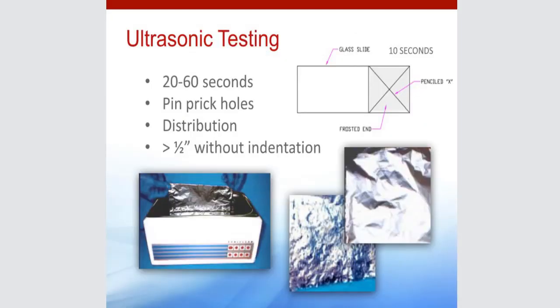Speaking of ultrasonics, these are my 2 public service announcements to deal with ultrasonic units. You want to make sure that you're following your IFUs for ultrasonic testing to make sure that your unit is functioning appropriately. The traditional foil test uses household aluminum foil, not the heavy duty like we use at the holidays, but traditional foil. You want to make sure that it does not touch the bottom or the sides of the tank when you're holding it suspended. And obviously you're going to do this only when you have new solution in the tank. You don't want to do it with dirty solution because you can't put the lid on it.